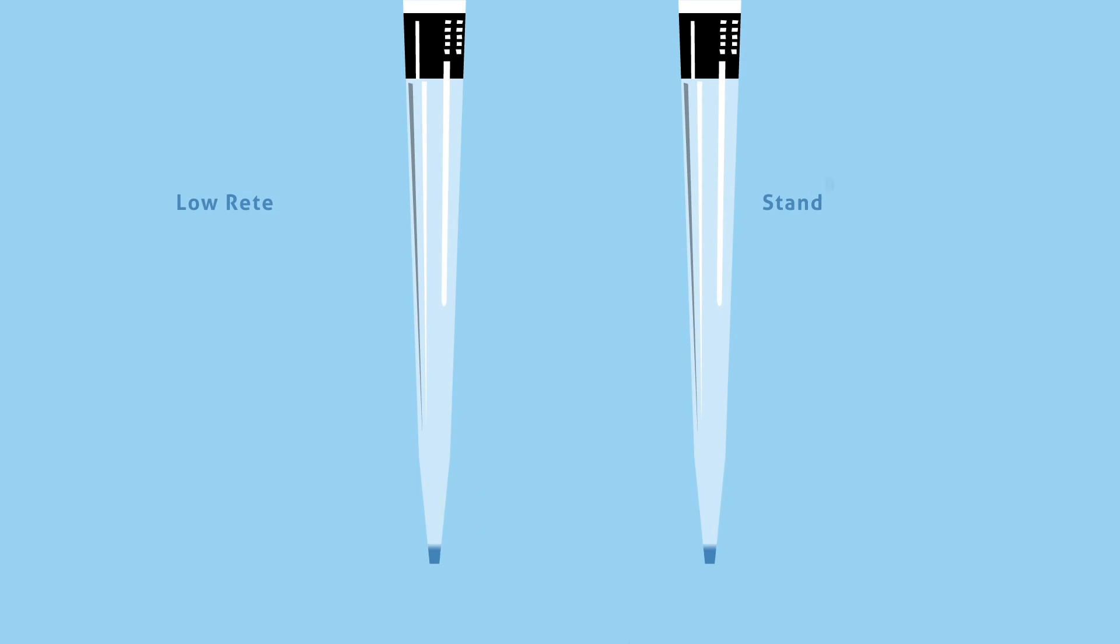To minimize error and to ensure accurate results, make sure your pipette tips fit properly. You shouldn't have to apply excessive force to apply the tip, and it should stay in place on the pipette. If the ejector doesn't work or there's liquid leaking, it may be the wrong tip. When using air displacement pipettes, all the liquid in the pipette tip is part of the measured volume.